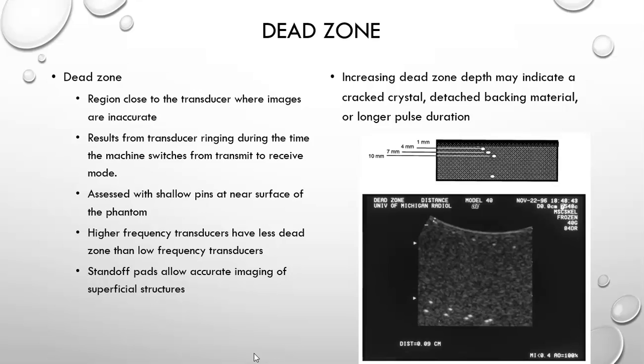With the newer machines, we're not seeing this dead zone at all, and that is because the newer machines are using different piezoelectric materials. They're not using PZT anymore. They're using polymers, and we're just simply not seeing the reverberation artifact in the near field that we used to. And so calling something the dead zone is almost a misnomer. I haven't seen a transducer really since 2000 that had a problem seeing the nearest pin of the dead zone, the 1 millimeter pin.